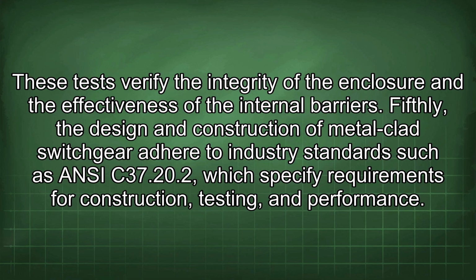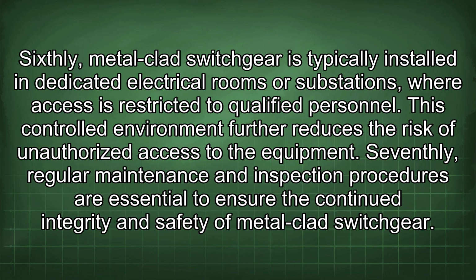Fifthly, the design and construction of metal-clad switchgear adhere to industry standards such as ANSI C37.20.2, which specify requirements for construction, testing, and performance. Sixthly, metal-clad switchgear is typically installed in dedicated electrical rooms or substations where access is restricted to qualified personnel. This controlled environment further reduces the risk of unauthorized access to the equipment.